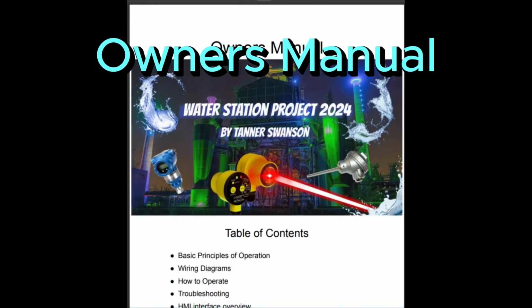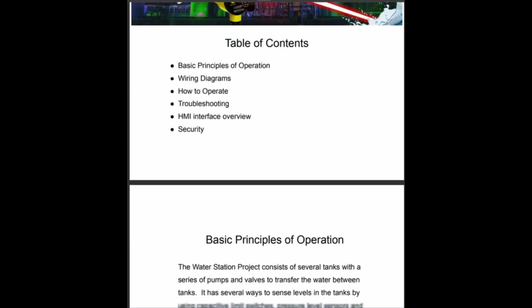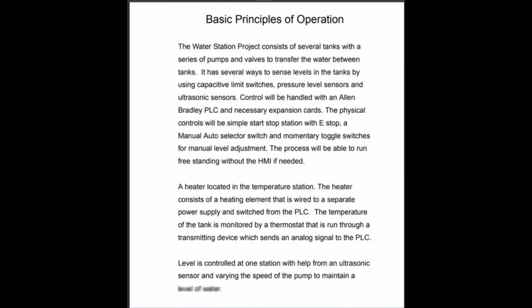First, going over the owner's manual. Basic operations. The water station project consists of several tanks with a series of pumps and valves to transfer the water between tanks. It has several ways to sense levels in the tank by using capacitive limit switches, pressure level sensors, and an ultrasonic sensor. Control will be handled with an Allen Bradley PLC and necessary expansion cards. The physical controls will be a simple start-stop station with an E-stop, a manual auto selector switch, and momentary toggle switches for manual level adjustment. The process will be able to run free standing without the HMI if needed.